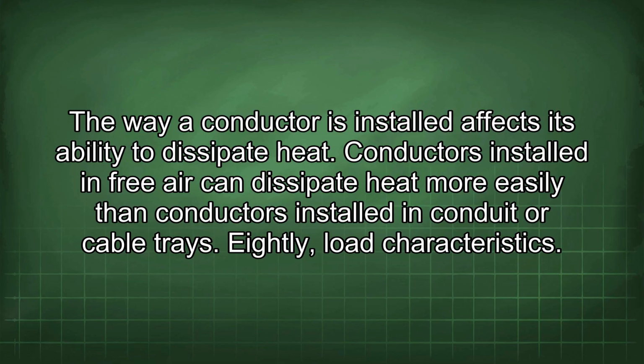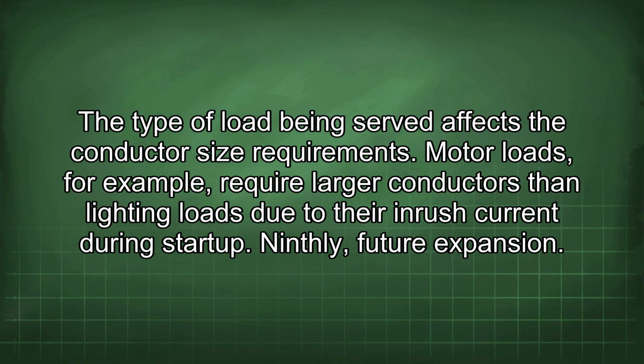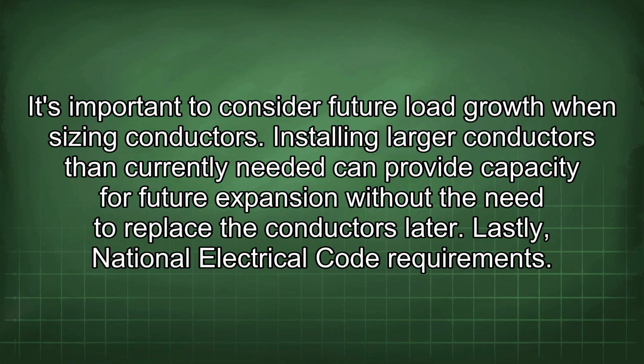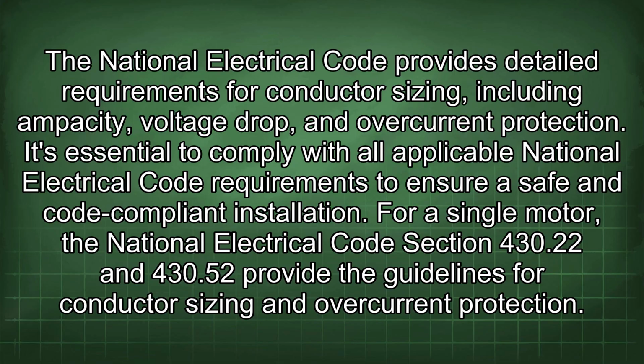Eighthly, load characteristics. The type of load being served affects the conductor size requirements. Motor loads, for example, require larger conductors than lighting loads due to their inrush current during startup. Ninthly, future expansion. It's important to consider future load growth when sizing conductors. Installing larger conductors than currently needed can provide capacity for future expansion without the need to replace the conductors later. Lastly, National Electrical Code requirements. The National Electrical Code provides detailed requirements for conductor sizing, including ampacity, voltage drop, and overcurrent protection. It's essential to comply with all applicable National Electrical Code requirements to ensure a safe and code-compliant installation.